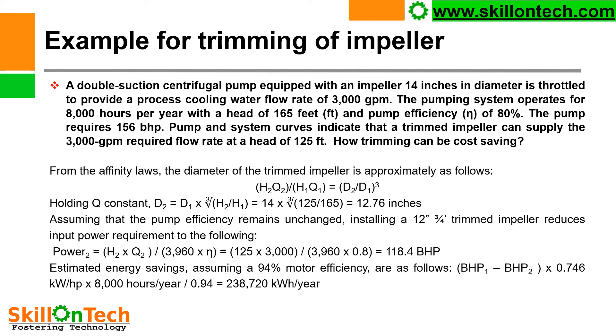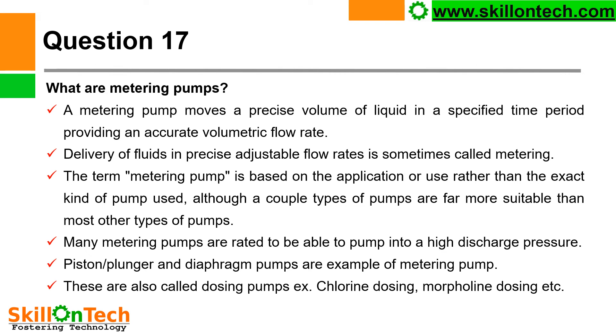Estimated energy savings, assuming 94% motor efficiency, are: (BHP1 − BHP2) × 0.746 kW/HP × 8000 hours/year ÷ 0.94 = 238,720 kWh per year.